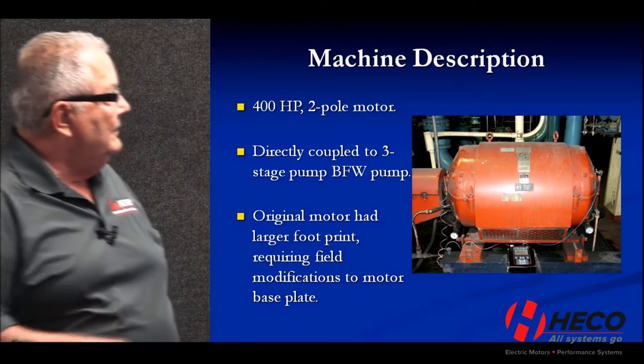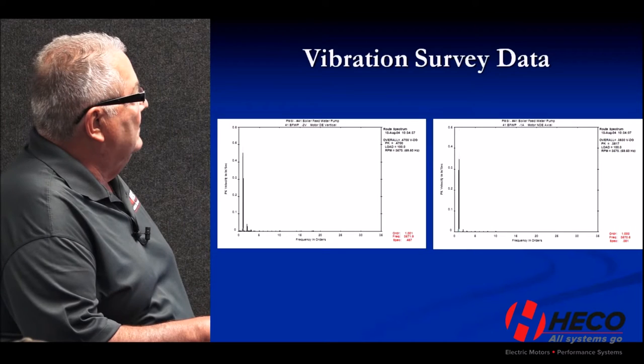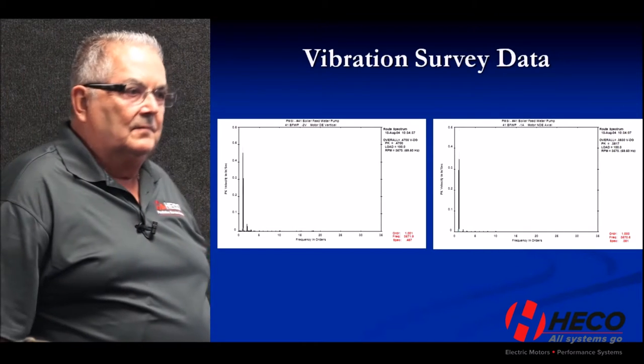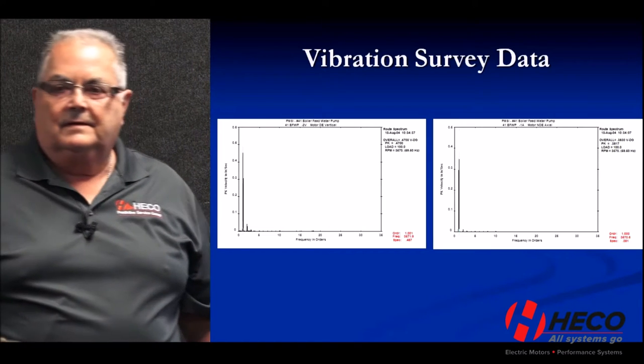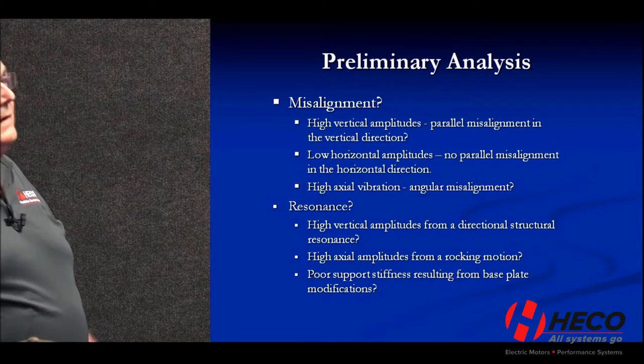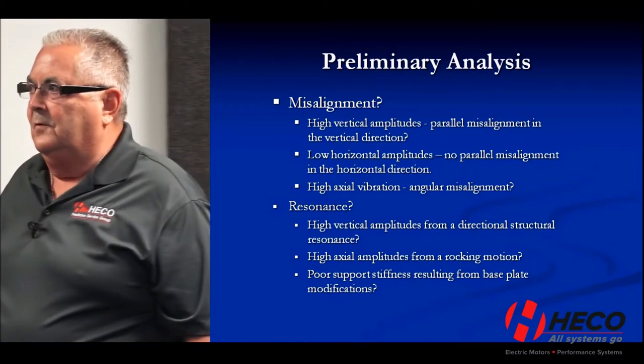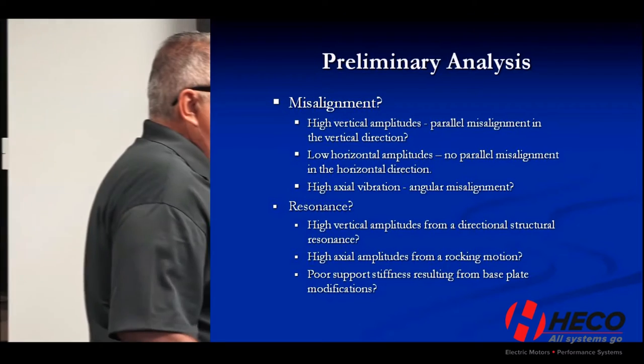We were taking readings with a data collector on both ends of the motor. The motor drive end vertical had 0.5 inches per second of vibration — higher than we would certainly like to see — all at one times the turning speed. The axial was 0.35 inches per second, again at the turning speed. Those were the highest peaks.